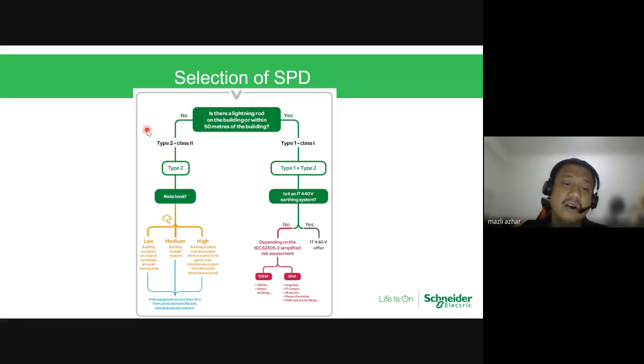So it's a medium risk. Or high risk, located in a special risk area where there's a pylon, there are high trees, mountainous region, mountain peak, okay, or nearby to a high building. So this is where the risk is high. For type 1 or class 1, normally from a manufacturer, we have type 1 and type 2 combined together, and then it depends on the earthing system. If it's not an IT earthing system, then you need to assess where it is located, for office, schools, for hospital, for IT center, for museum. So this is, like I say, the starting point when you want to select an SPD, to select the correct SPD for the building.